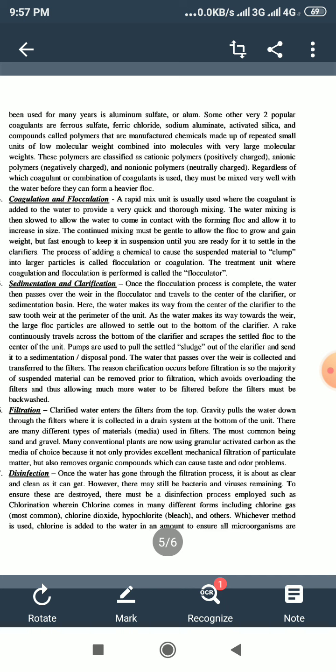Next is sedimentation and clarification. Once the flocculation process is complete, the water then passes over the weir of the flocculator and travels to the centre of the clarifier or sedimentation basin. Here the water makes its way from the centre of the clarifier to the saw-toothed weir at the perimeter of the unit. As the water makes its way towards the weir, the large floc particles are allowed to settle out to the bottom of the clarifier.